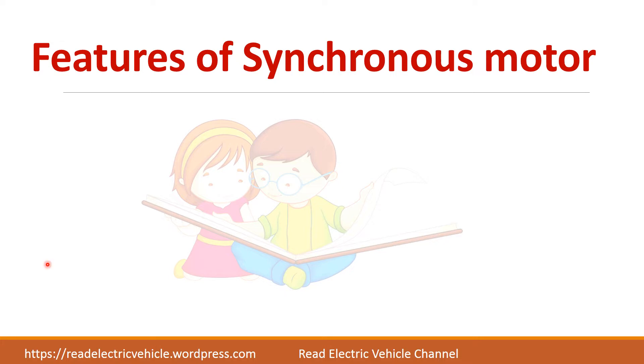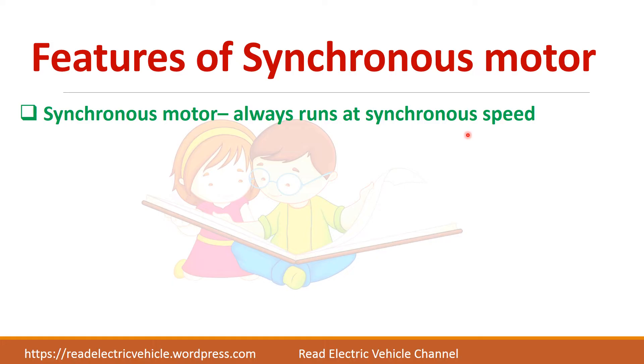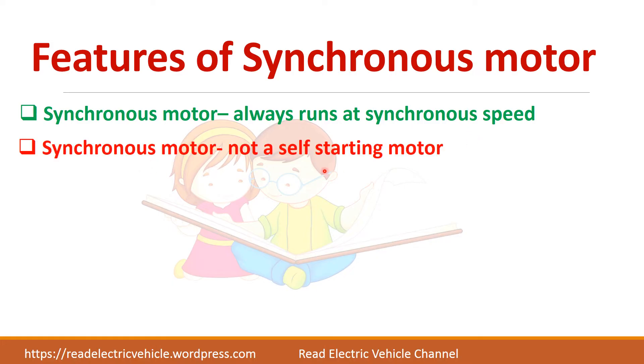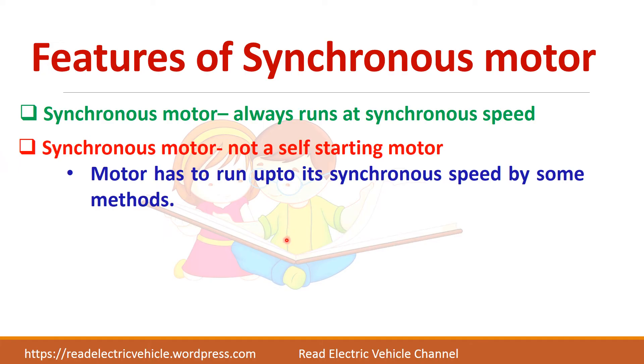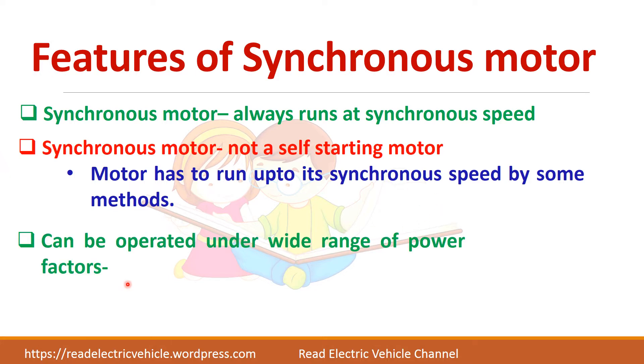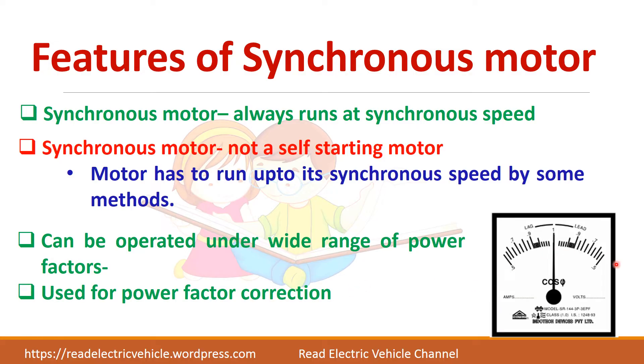The features of the synchronous motor: first, it will always run at synchronous speed. But it is not a self-starting motor — when you give the supply, it will not start on its own. You have to start the motor and bring it up to synchronous speed so that the stator and rotor will lock into synchronism. The main advantage of the synchronous motor is that it can be operated under a wide range of power factor — both lagging and leading — and it can be used for power factor correction, which is one of its major applications.